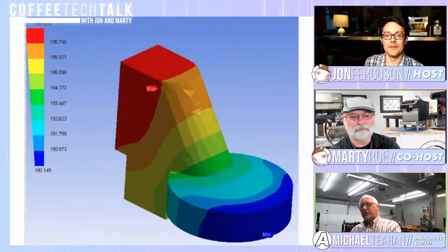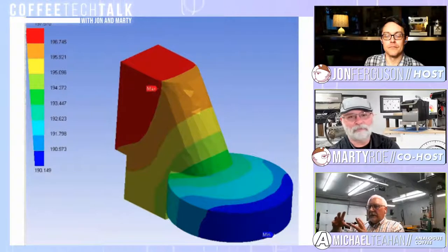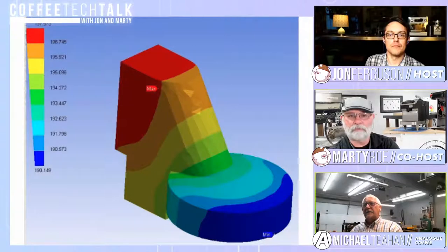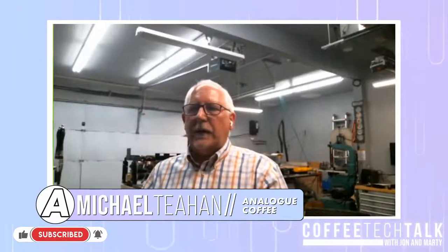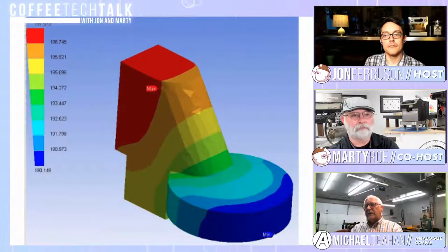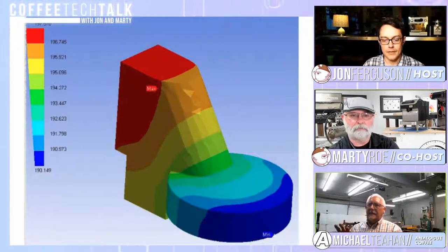The reason brewing groups are either attached to or separated from the boiler in such a way is that they're always radiating heat. So how is it that you can get water out of a boiler that's 120 degrees Celsius, but it's only being delivered at, let's say, 92? That's because it's always dissipating heat. It's passing through flow restrictors, expanding as it goes through them, which has kind of a refrigeration effect. This was actually a temperature map of how much heat is being dissipated the further you are from the group itself. So all this stuff is kind of designed into the machine.